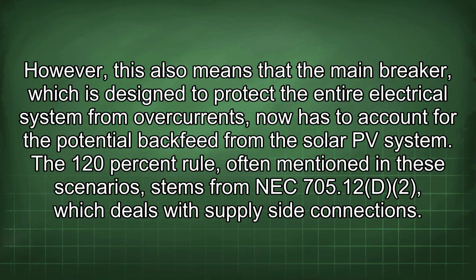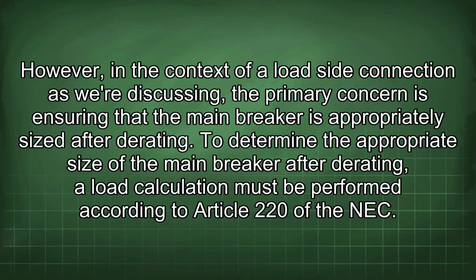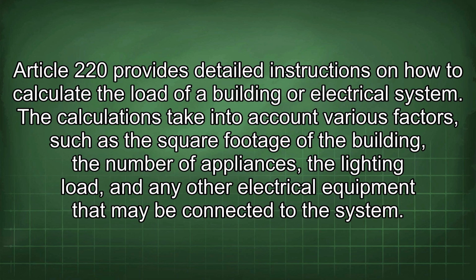The 120% rule, often mentioned in these scenarios, stems from NEC 705.12(D)(2), which deals with supply-side connections. However, in the context of a load-side connection, as we're discussing, the primary concern is ensuring that the main breaker is appropriately sized after derating. To determine the appropriate size of the main breaker after derating, a load calculation must be performed according to Article 220 of the NEC. Article 220 provides detailed instructions on how to calculate the load of a building or electrical system. The calculations take into account various factors, such as the square footage of the building, the number of appliances, the lighting load, and any other electrical equipment that may be connected to the system.